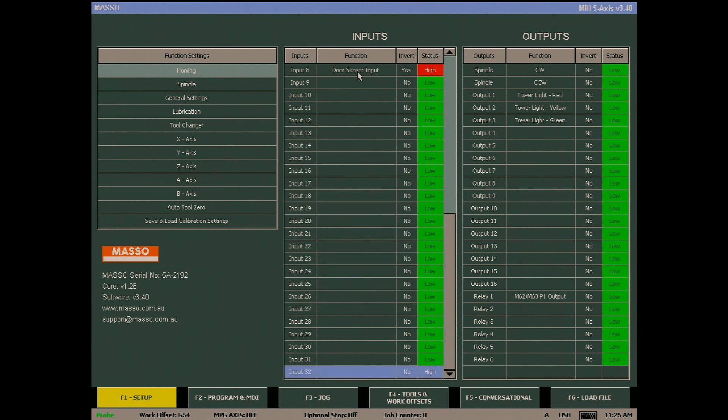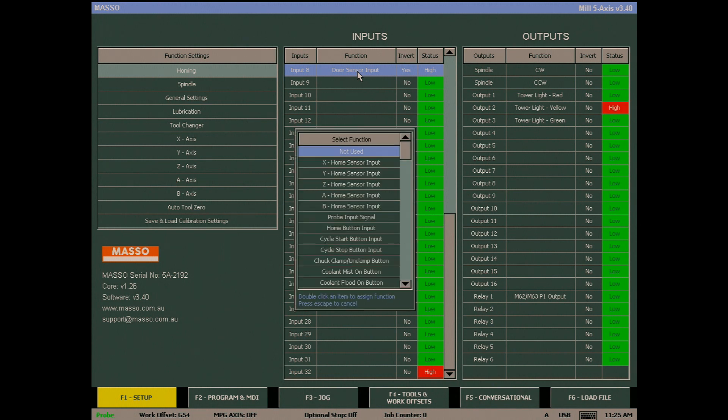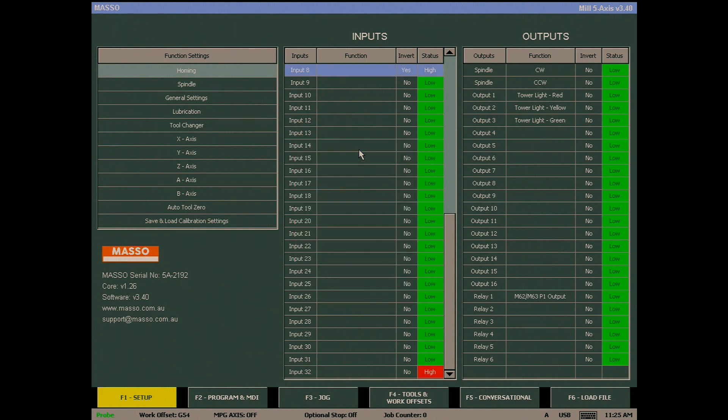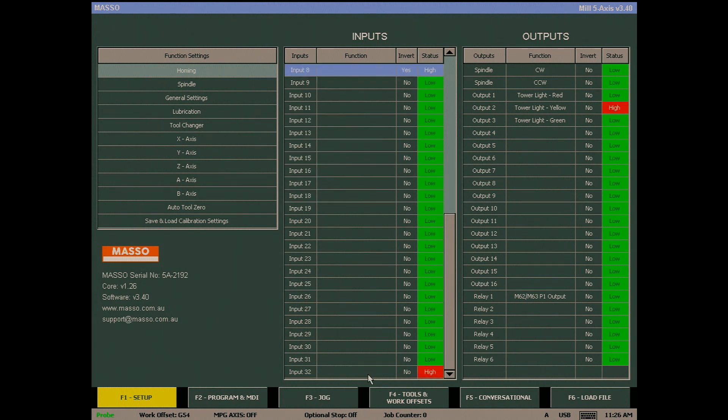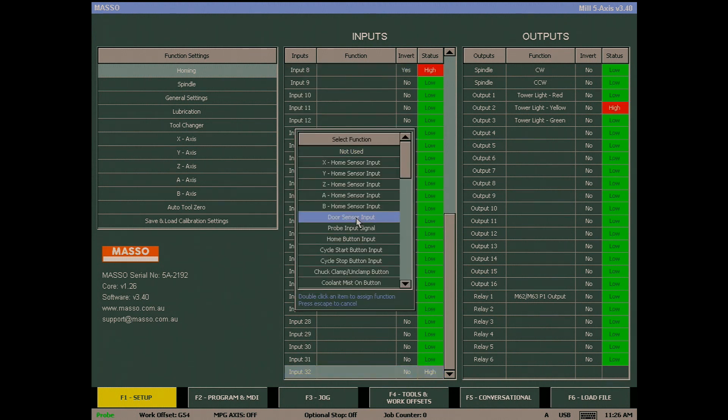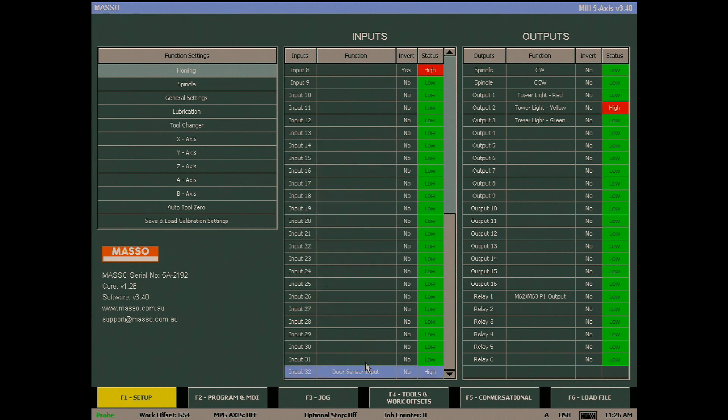To make the door sensor input available, I first need to delete input 8 by double clicking on the function box of input 8, and then double click the Not Used option. I then move down to input 32, double click the function box, and double click to assign the door sensor input function to the input.